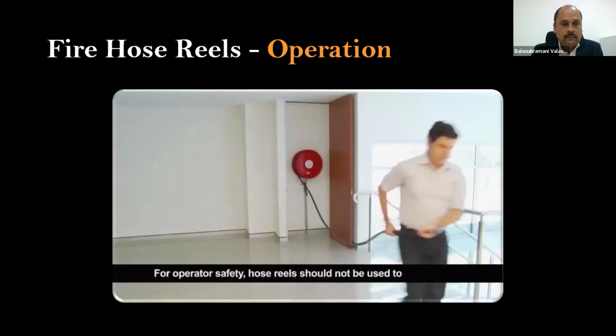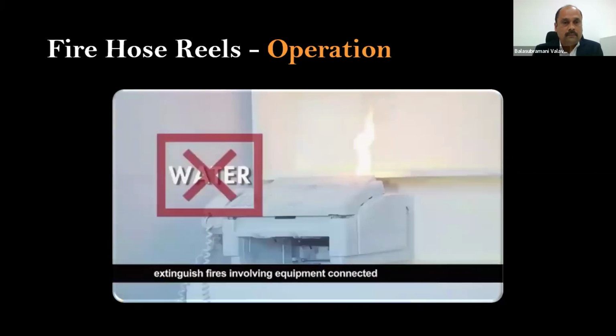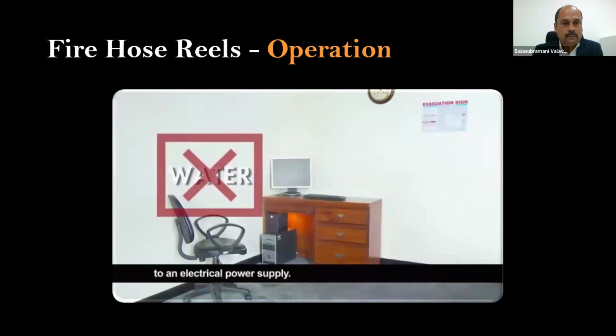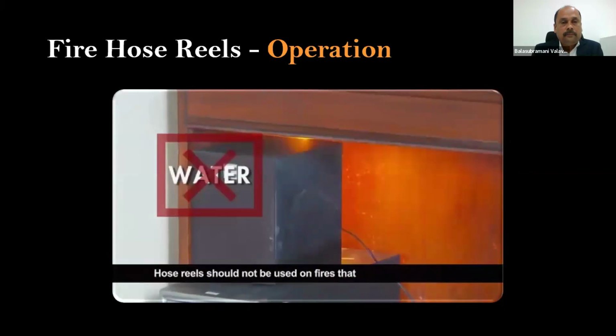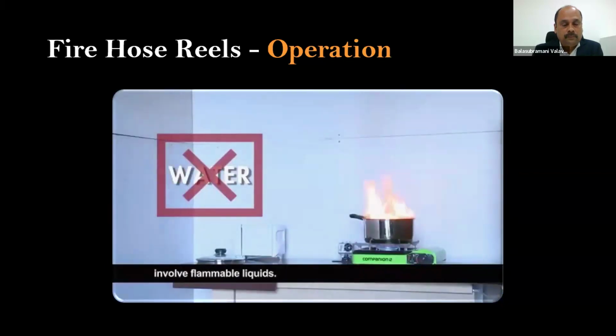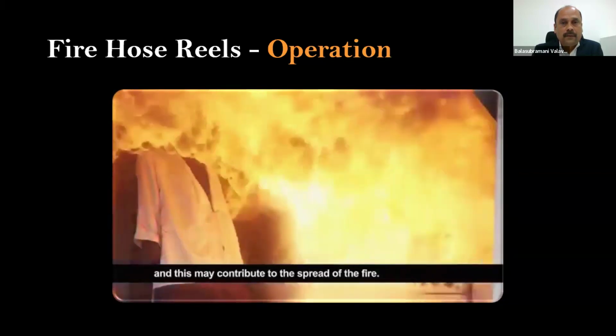For operator safety, hose reels should not be used to extinguish fires involving equipment connected to an electric power supply. Water is a good conductor of electricity. Hose reels should not be used on fires that involve flammable liquids. Burning liquids will float on the surface of the water, and this may contribute to the spread of the fire.